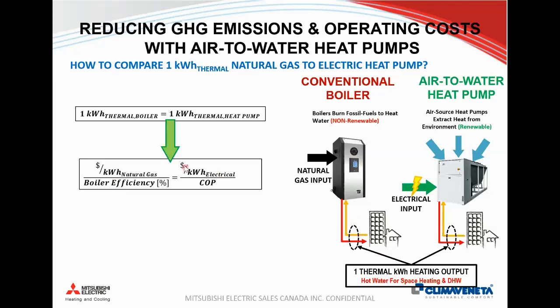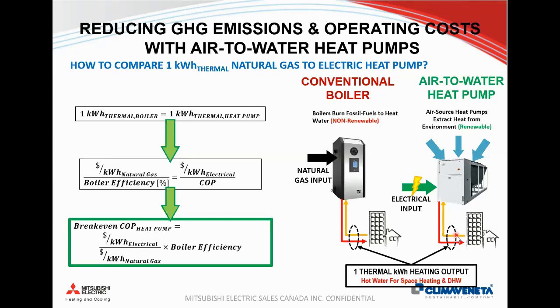And we do the same for the heat pump. We take our delivered cost for electricity, in dollars per kilowatt hour, and divide it by the COP. That's how much money we're spending for the same amount of heat. We can essentially rearrange this equation and figure out what break-even COP we need in order to be cost neutral, based off the ratio of cost between electricity and natural gas, and express it like this.